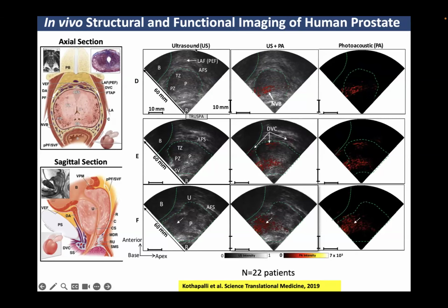As you can see, this left one is an ultrasound image of the prostate, and the right one is the photoacoustic imaging of the prostate, and the middle is the ultrasound co-registered photoacoustic image. Right, all of them are displayed in real time. Ultrasound frames are 30 frames per second. Photoacoustic frame rate is about 10 frames per second, mostly limited by the laser firing rate. The lasers that I use for this deep tissue imaging can fire only up to 10 pulses in 1 second, so we can have 10 frames per second. So this co-registered frame is also updated about 10 frames per second.